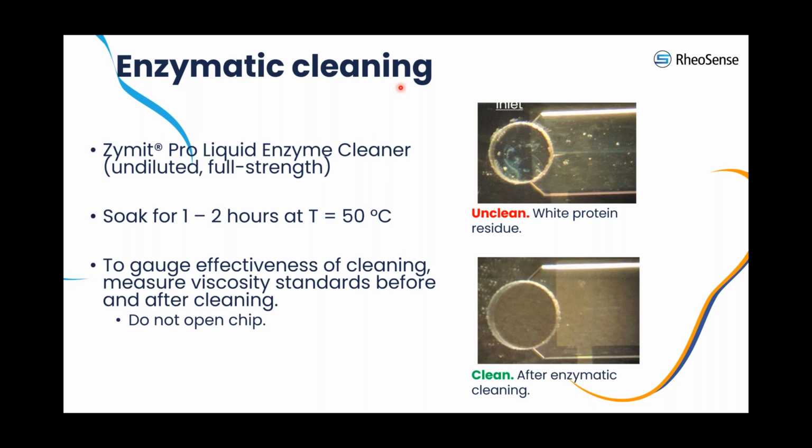As shown in the image here in this slide, you can clearly see the chip before and after Zymit cleaning. The difference is evident, with the Zymit solution successfully removing protein residue from the chip. This process significantly enhances the quality and accuracy of the data you can obtain. Now I'm going to turn it over to my colleague, Dr. Ochoa, and he's going to go over some details about chip maintenance and start sharing some good and bad data with you.